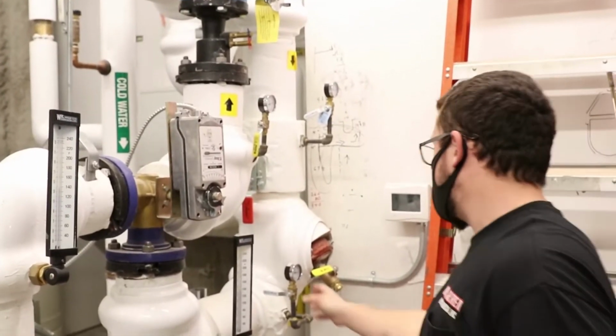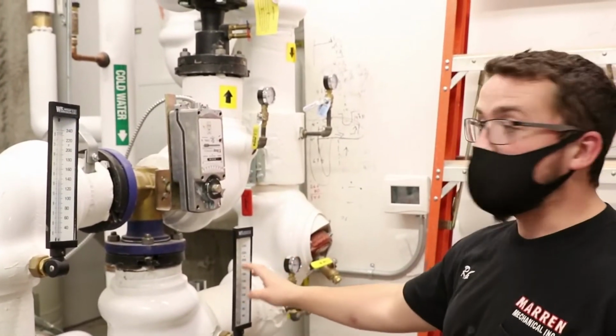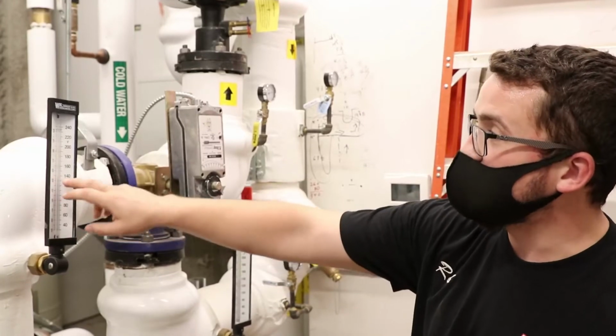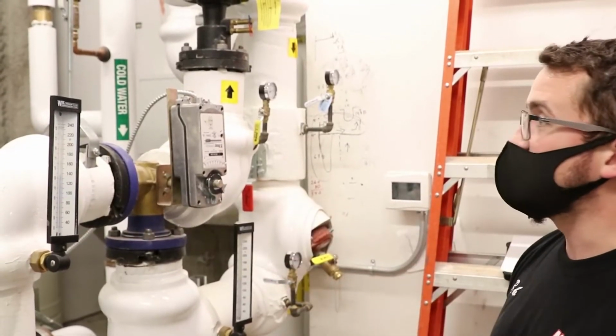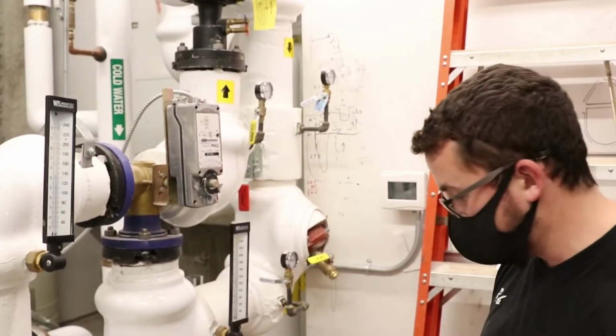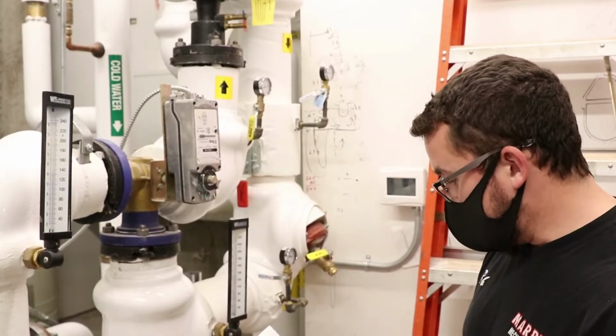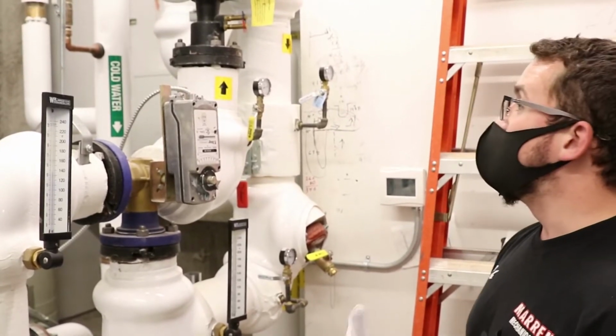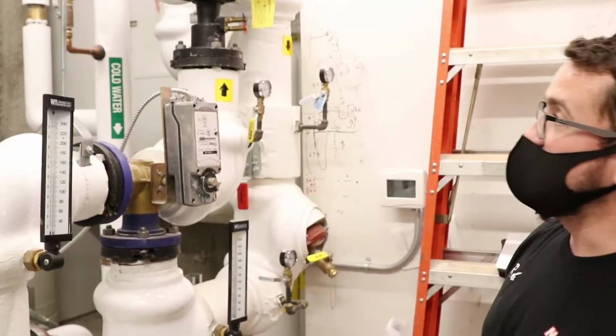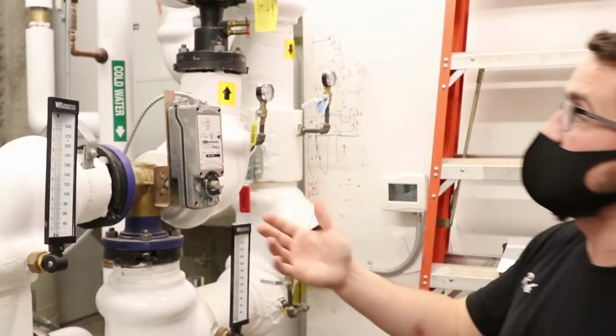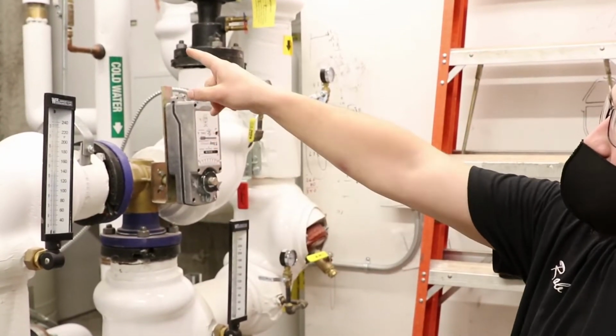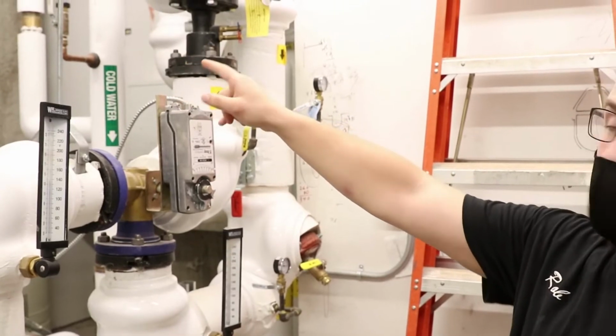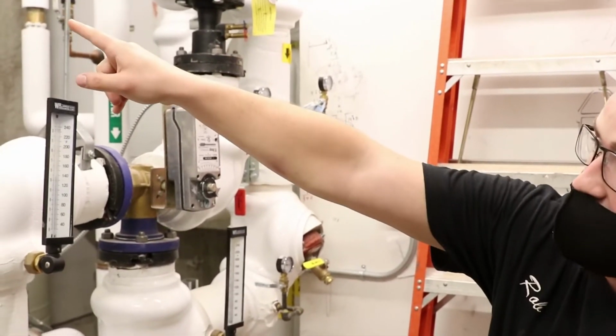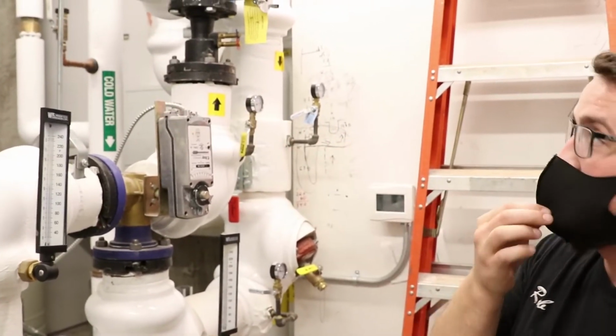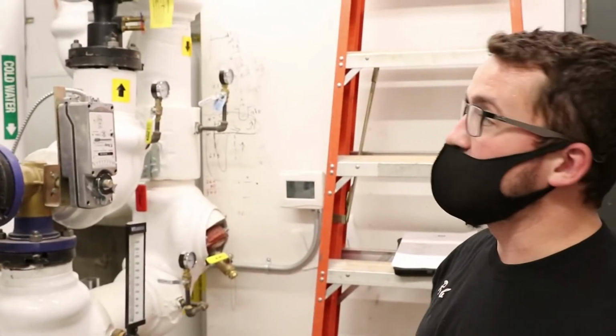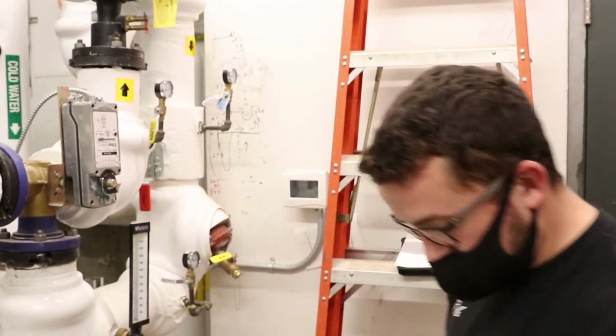You're going to want to take note of what these numbers are and make sure that these gauges are accurate and that they haven't failed and that they're still providing you with good and useful information. Same thing goes for those two numbers on the heater. You can easily check those like I touched on earlier. You look at the number that is shown on the display and then look at the gauge that's on the outlet hot water piping, and those numbers right now match perfectly, and they always should.